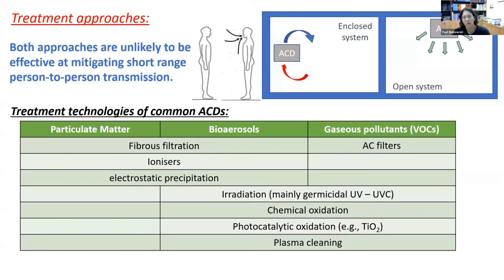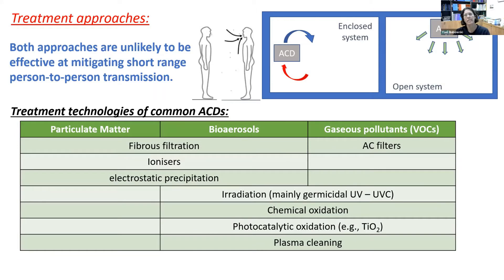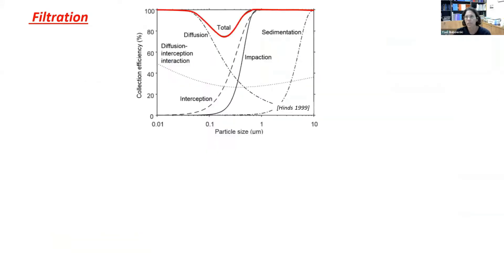With regard to the technologies for treating those three categories of pollutants: for particulate matter — whether general PM or bioaerosols — we have filtration, ionizers, and electrostatic precipitators. For VOCs, we can have sorption on a sorbing media for removal from indoor air, but to actually degrade them, when dealing with bioaerosols or VOCs, we use irradiation — mainly UV radiation — or chemical and photochemical oxidation, as well as plasma cleaners.